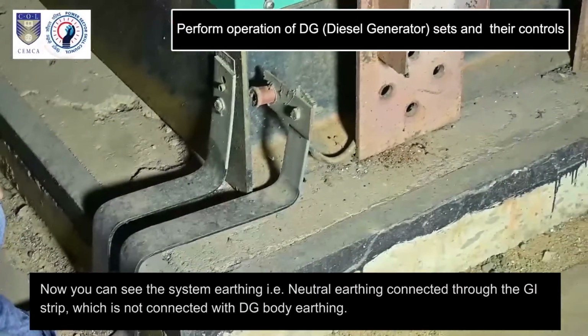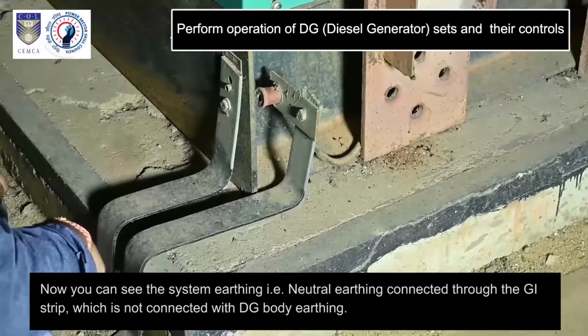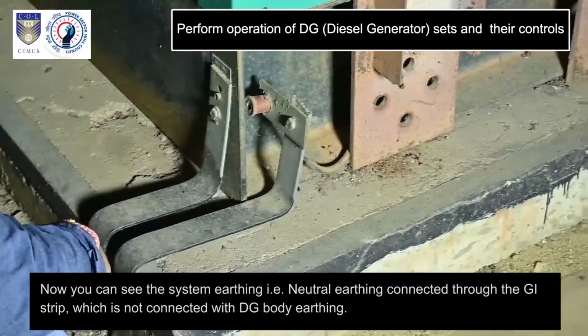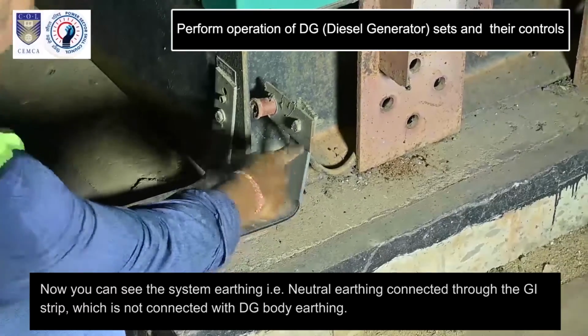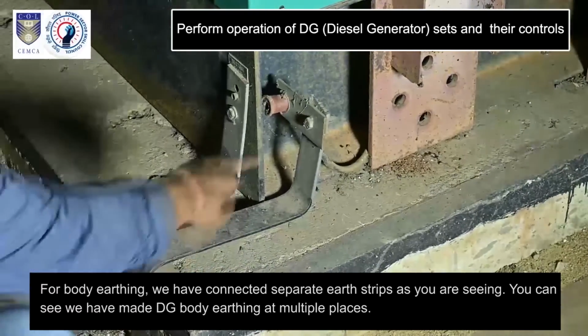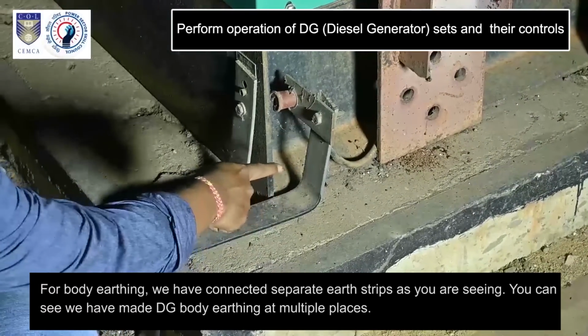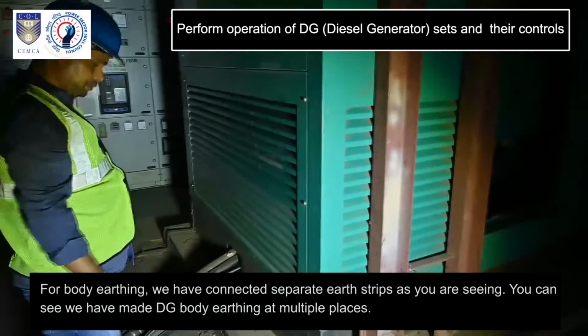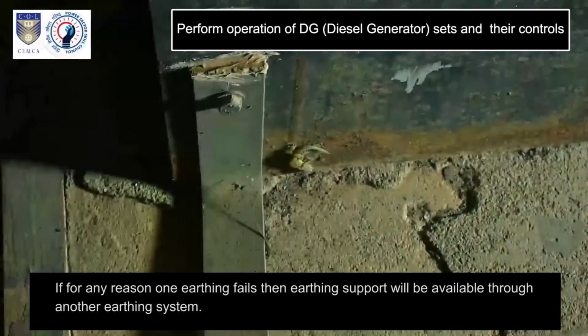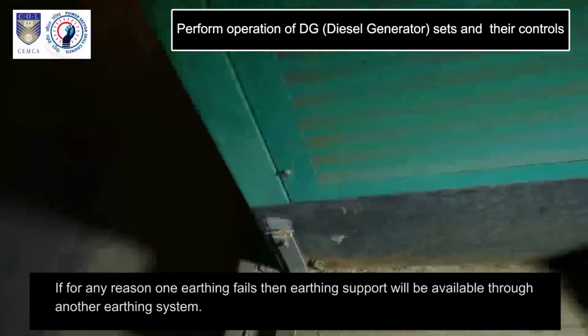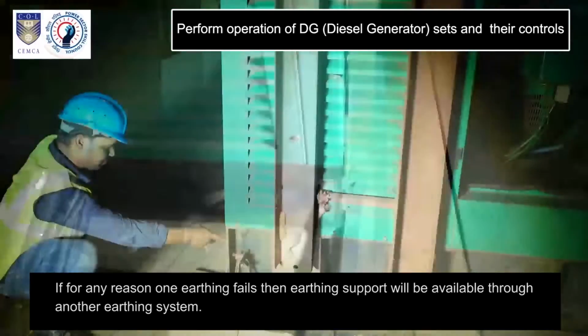Now you can see the system earthing, that is neutral earthing, connected to the GI strip, which is not connected with the DG body earthing. For body earthing, we have connected separate earth strips, as you are seeing. You can see we have made DG body earthing at multiple places. If for any reason one earthing fails, then earthing support will be available through another earthing system.